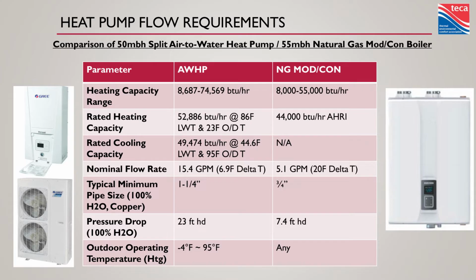We really need to understand the relationship between the heat source and the load as the outdoor temperature changes. A couple other distinctions here. Well, that air-to-water heat pump can cool. The boiler cannot, so that's a thing. Flow rate, 15.4 gallons per minute. That's a 6.9 degree delta T. What's the boiler want? 5.1. Same BTUs, 50,000 BTUs roughly each of these appliances.